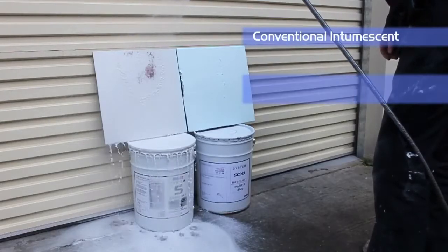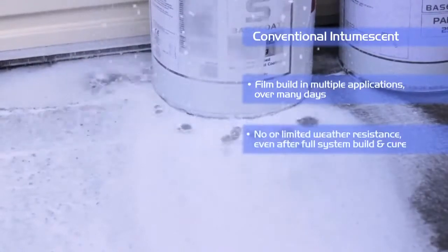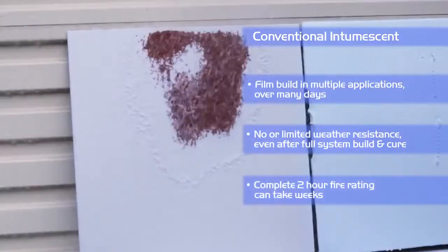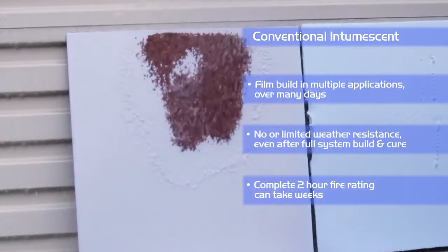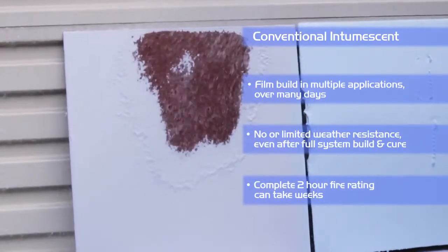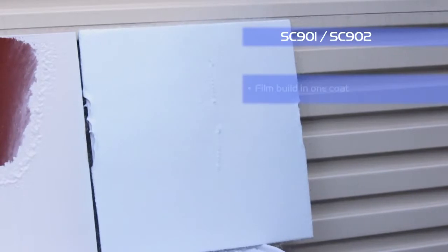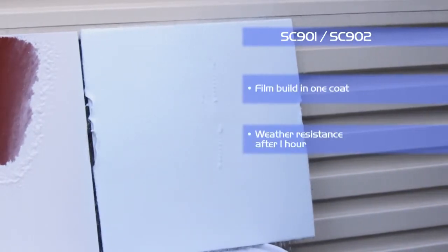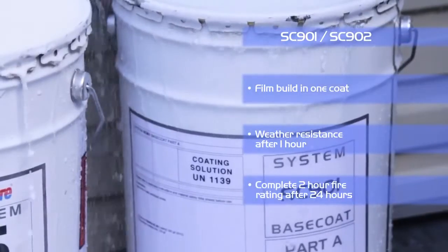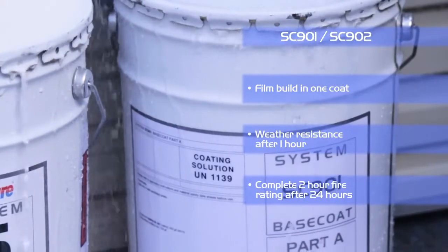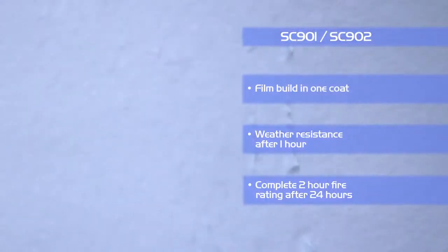Conventional intumescence have limited resistance to environmental conditions during the construction phase and can be easily washed off. The off-site SC901 system is touch dry, weather resistant and over-coatable within 60 minutes. Where required a top seal can be applied the same day and can be transported within 8 hours of coating.